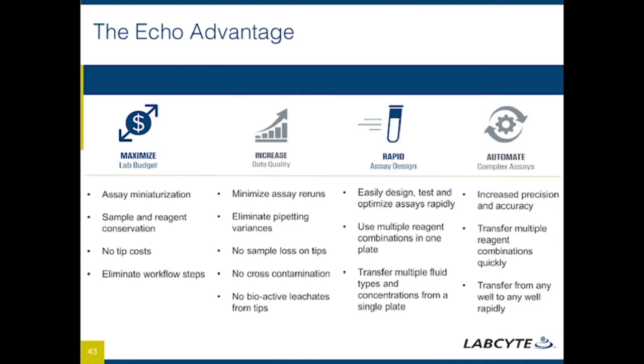So the advantages of the Echo liquid handler really fall into four major buckets here. The first one is maximizing that lab budget, and that's primarily through that miniaturization, but also the elimination of consumables such as tips. The second one is data quality, the ability of the instrument to very accurately transfer a predetermined volume and to do that very precisely, which is going to result in very consistent assay results time and time again. The speed at which the system is capable of transferring liquids, the ability to do any well to any well transfer, of course, translates into a very rapid assay design process. And then lastly, the need to automate complex workflows and the increased precision and accuracy that comes through that automation, as well as the ability to free up time for perhaps other higher value activities within the lab.